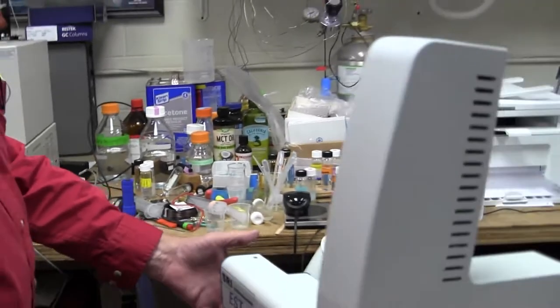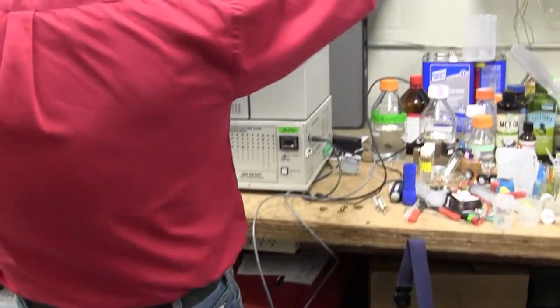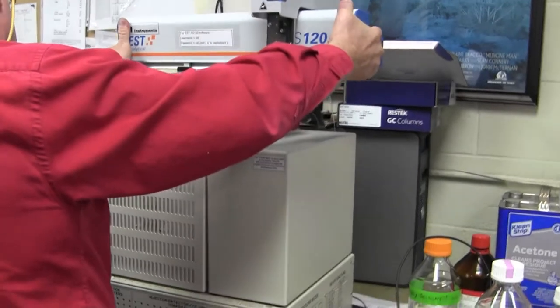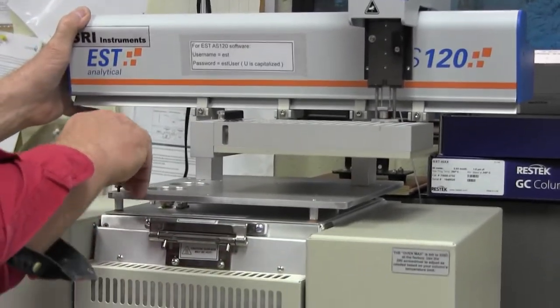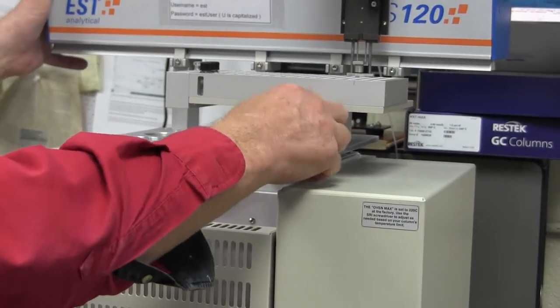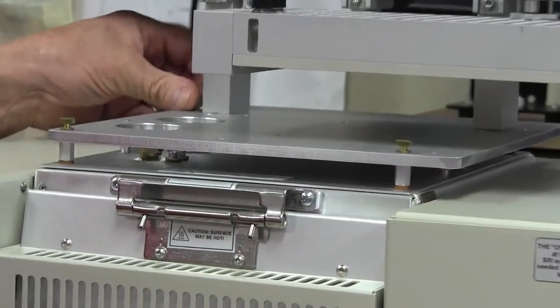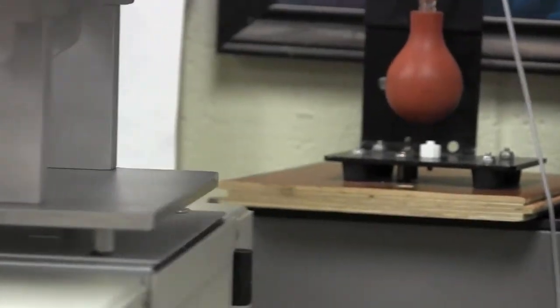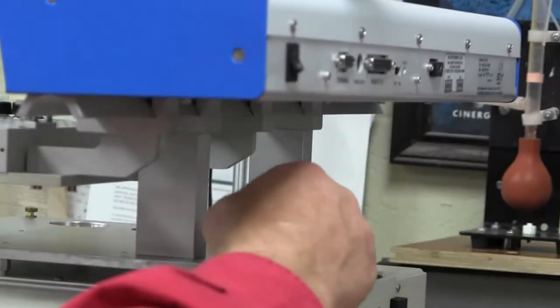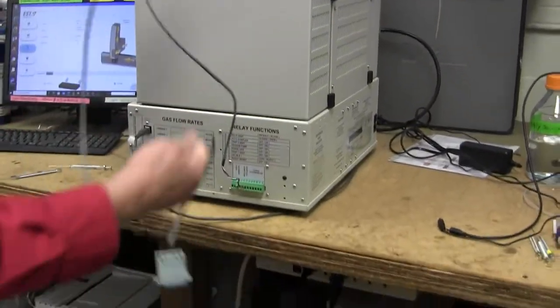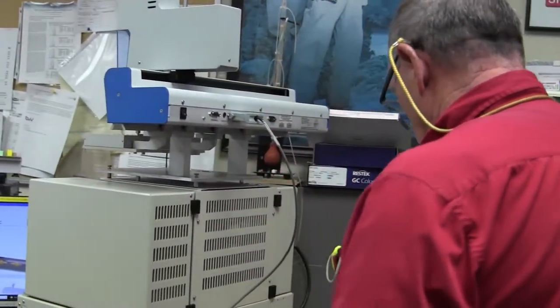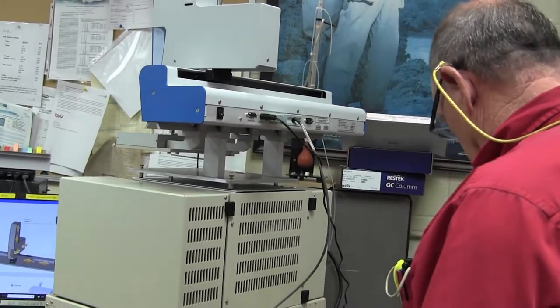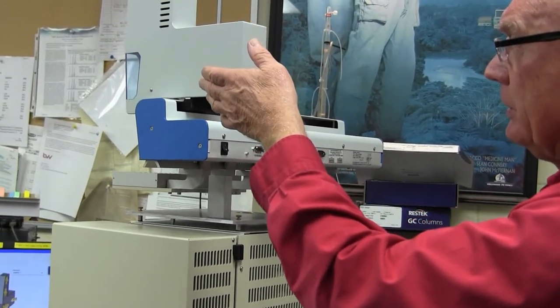Okay so I'm going to take the auto sampler now and put it back on the GC. So here we go and those two little prongs have to line up and go in the two existing little holes and that aligns everything together. So then you put the set screws back. So then the cable that goes between the GC and the auto sampler, we're going to take the little plug back in there and then the power. I think it's 24 volts and I hear something happening and something moving when I plugged in the power.